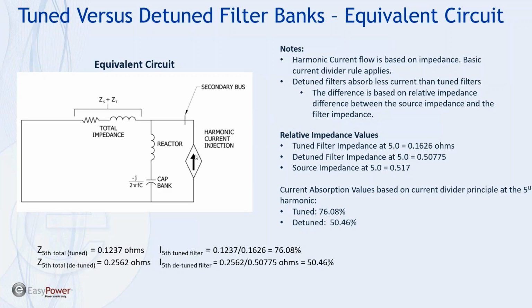So harmonic current injected from the VFD drives or nonlinear loads are ideal current sources, and therefore the current that's injected here, when it gets to this point, has a choice. It either will flow towards the filter or flow towards the source. The choice here, or the value of current flow, is just a current divider. It's that simple. It's a ratio of impedances between the total impedance of the source relative to the total impedance of the filter branch.